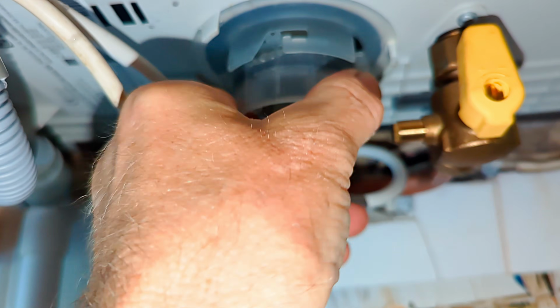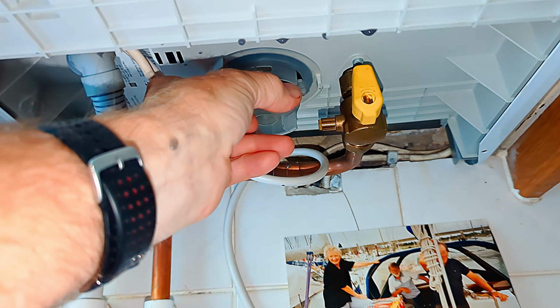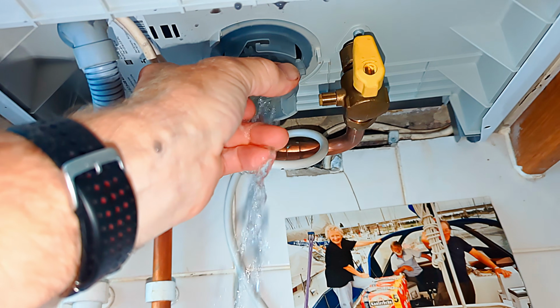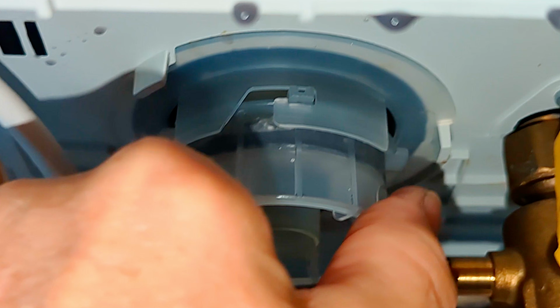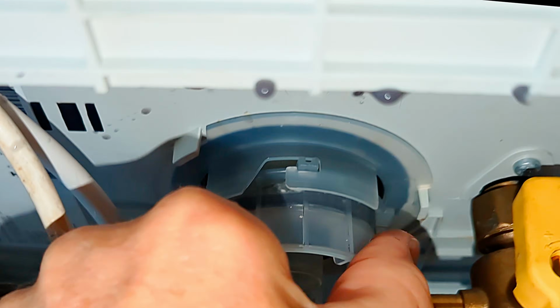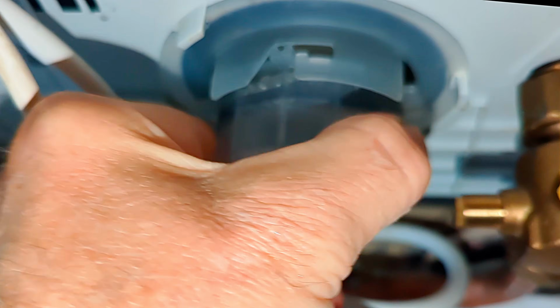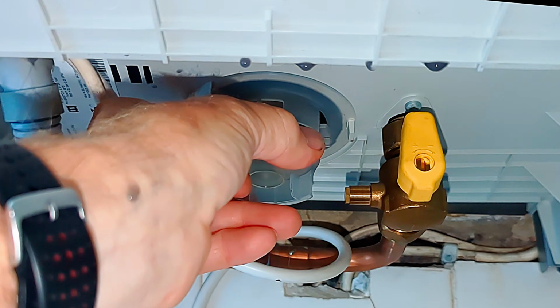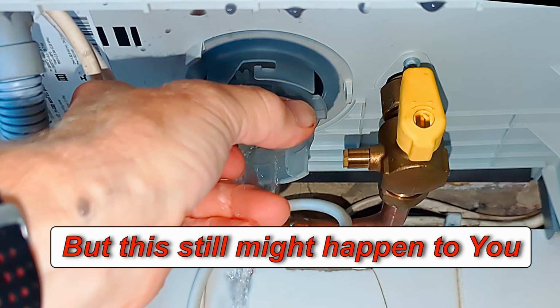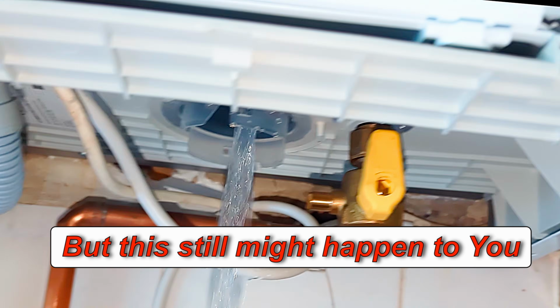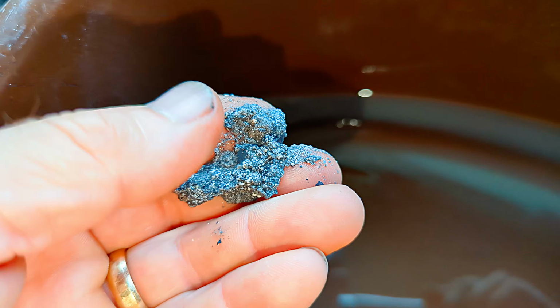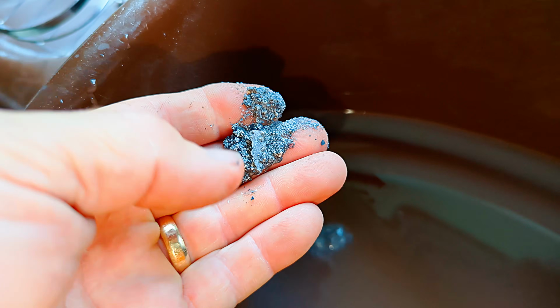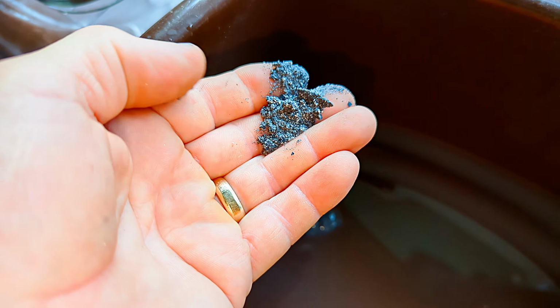Now this is straightforward. You just hold that middle plastic part, push it up very slightly, rotate it around anti-clockwise, and then pull it down. Hopefully you can see there's two bayonet style retainers holding the trap in place. Now when I removed the trap originally, still no water ran out of the bottom of the boiler. Because the blockage isn't in the trap, it's in the bottom of the heat exchanger, where the water runs down through the hole and into the trap. So aluminium oxide is blocking up the hole and not allowing water to run out through the hole.